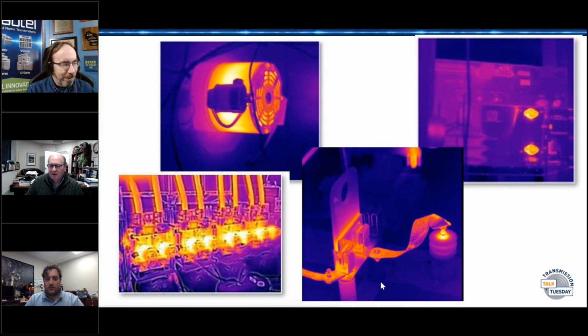The thing in the lower middle is mostly reflections and emissivity issues, that's shiny stuff. However, the right-hand strap is going to a coax where it's kind of bolted in with a nut and a compression fit on the inner conductor, and that's not making as good a connection as I'd like. You can also see the threads on the connector there, a little bit of corona is giving you that heat effect. So I'm not worried about the J plug, I'm not worried about the strap, but I am worried about the connection to the transmission line. Maybe I should take it apart, look at it, see if I can remake that connection.